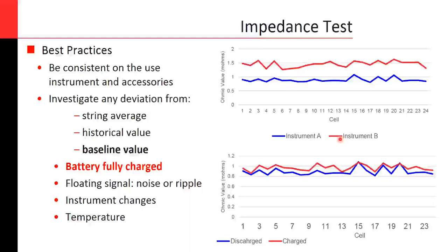Also, for the best practices, again, the battery should be fully charged. If there's any deviation from the values that you were obtaining previously, you want to verify that the float current is not too high, that the battery is not charging at that moment, or that there's no noise or ripple in the system. Also check if there's any instrument change, or if there's any temperature change from the previous measurement.